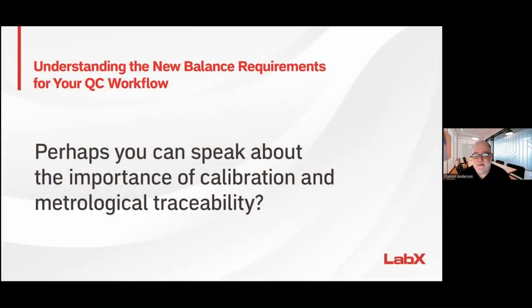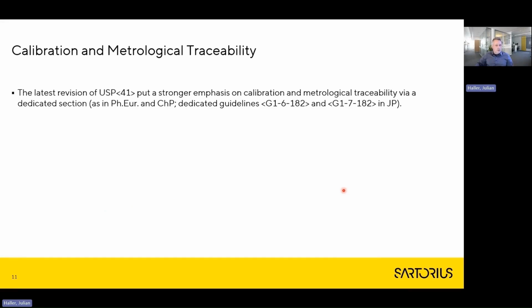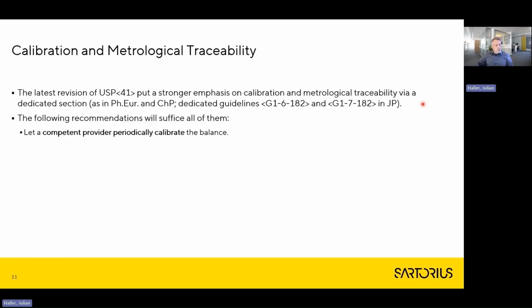Perhaps you can speak about the importance of calibration and metrological traceability. The latest revision of USP Chapter 41 has put a much stronger emphasis on these topics. A dedicated section was introduced, like it already existed in the European Pharmacopoeia and the Chinese Pharmacopoeia. In the Japanese Pharmacopoeia, there are dedicated guidelines G16182 and G17182 concerning calibration and metrological traceability. If you follow the following recommendations, you will satisfy all of the requirements and will be on the safe side. Let a competent provider periodically calibrate the balance. It should be mentioned that worldwide accreditation is accepted as proof of competence. So if you have an accredited calibration laboratory periodically calibrate the balance, you will be on the safe side here.